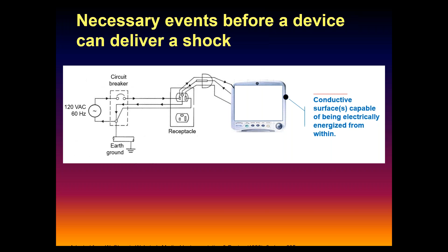First, you have to have a conductive surface on the device capable of being energized. The struggle today is finding devices with a conductive surface. There might be a ground pin on the back that just gives you a ground resistance check, but there's nothing conductive on the surface of these machines, even our beds, that can be energized from the inside.